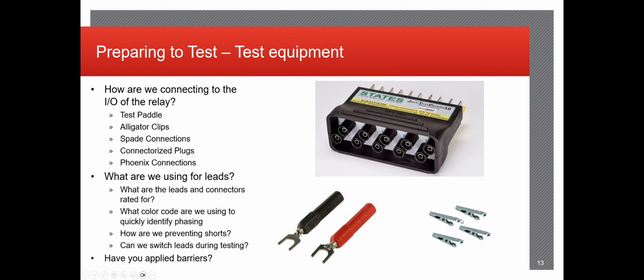Alligator clips, which you see in the bottom right, I actually don't necessarily think are a useful tool to utilize when you're relay testing, because the back of the relay terminal blocks, the screws are so small, and those alligator clips, unless they're super tiny, are probably not going to get a great connection, especially when you have to unscrew the bolt as much as possible. As well as, in this example, you can see that they're uninsulated, so that could also lead to damage to the relay or the test set, or possibly injuring yourself too, especially if the test set is pushing DC.